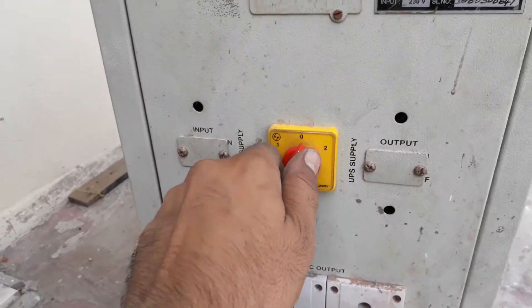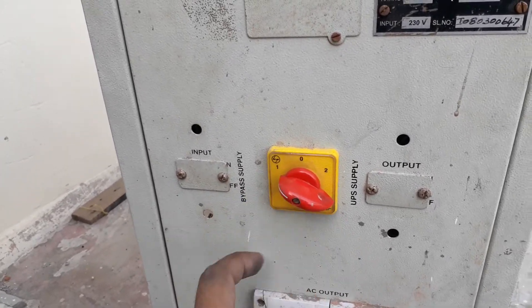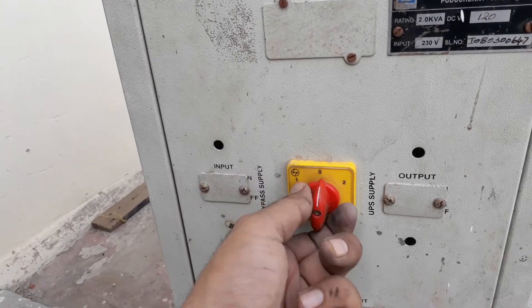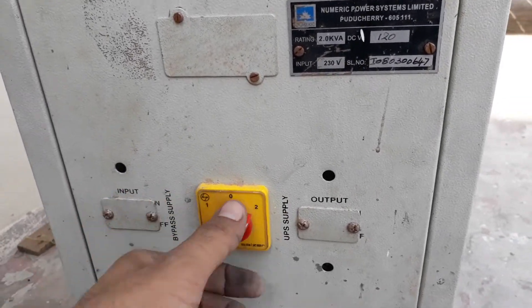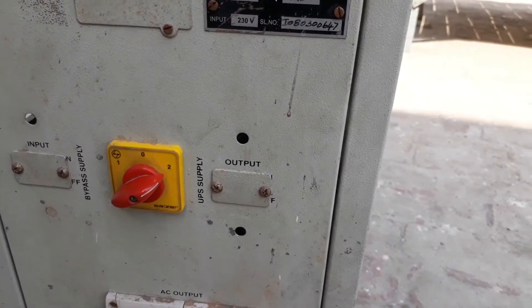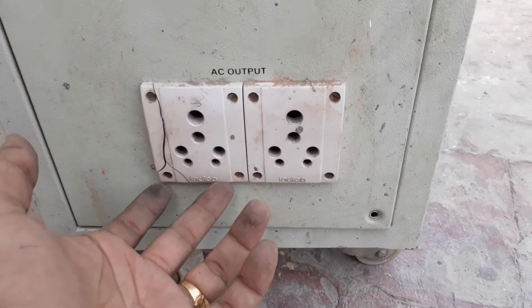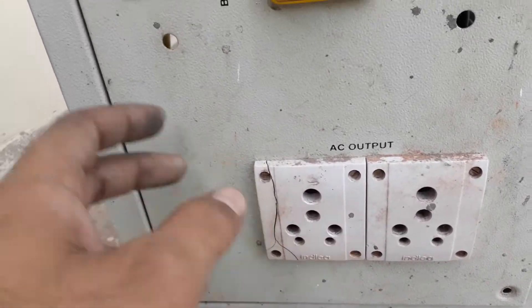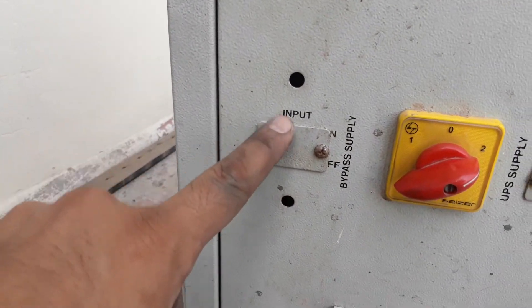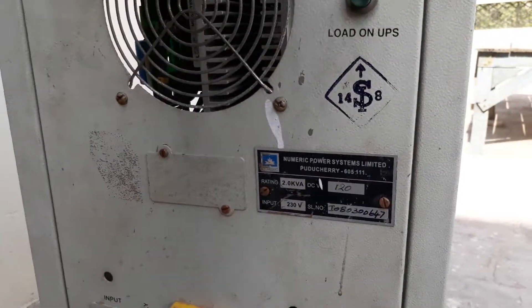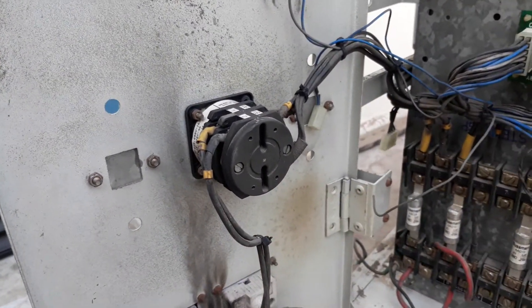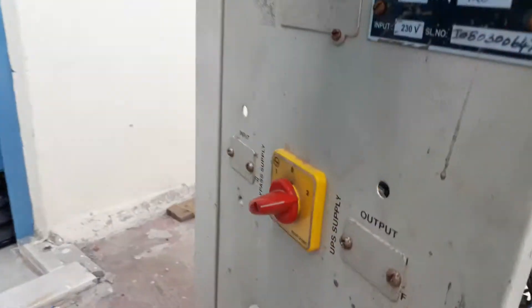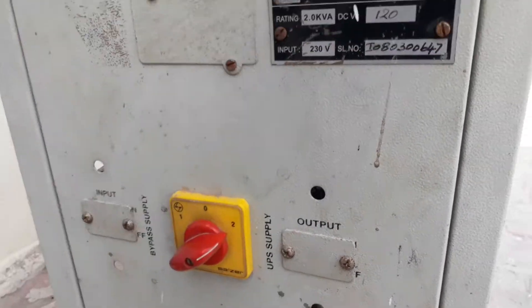They also provide an optional output. If anyone wants a bypass supply, they can bypass it. If the customer wants UPS supply, they can use UPS supply. They also provided two sockets, 16 amperes and 220 volts, and options for input MCB and output MCB. Right now, the MCBs are not present.